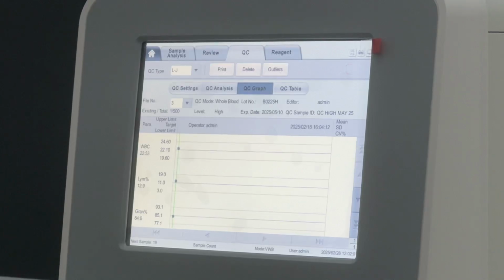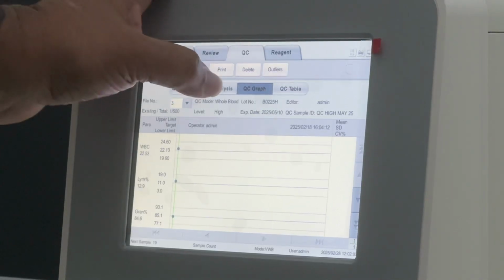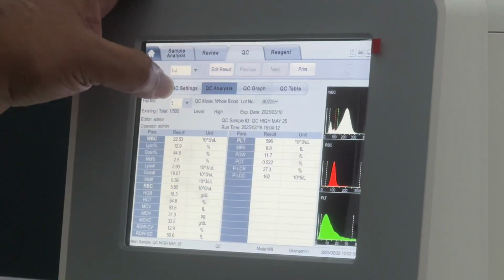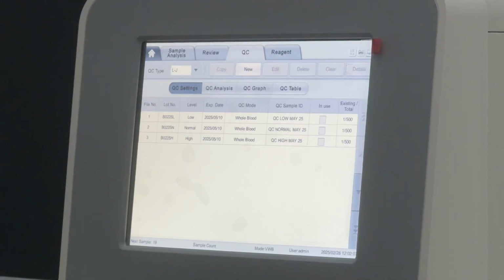Based on these 3 levels, we need to do the analysis on the QC also. So every 3 months our engineers will come, do the calibration, do the QC, check the machine, and do the PPM as well. They put all the data inside, so at least they know the machine is working properly and the range is within everything.